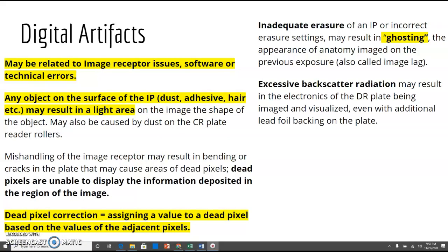A potential artifact using CR cassettes is when the plate doesn't erase completely. You'll see remnants of other anatomy or someone else's lead marker — it's sometimes called ghosting. It just didn't erase properly. Or there could be excessive backscatter radiation, which deals with the lead foil backing on the plate.